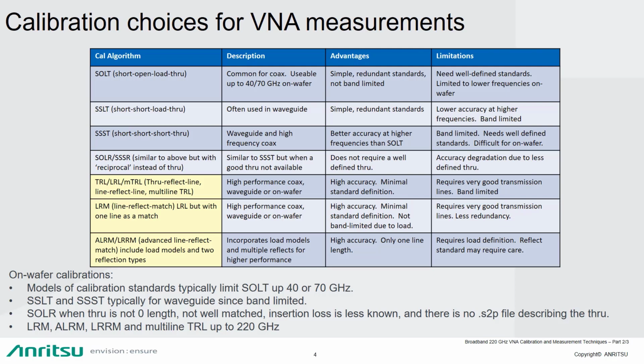The SOLR is similar to the SOLT, except that the through may not be well defined or available, at least a good through. And so you would just use a reciprocal through and get your calibration coefficients through that process. There's a slight degradation in accuracy because it's taking some assumptions, but if that's all you have, then that would be a way to approach the situation where you don't have well-defined throughs.